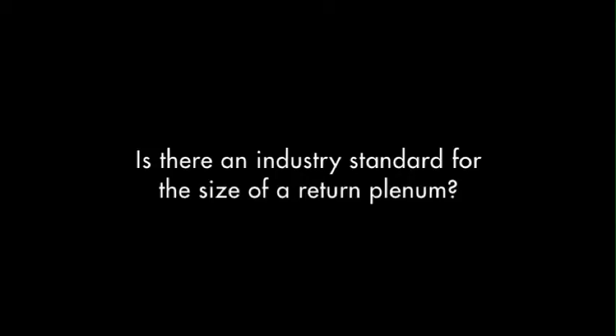I've not really run into any constraints about it being too big. I have run into constraints about it being too small. Fortunately, there's a relatively simple device called a Ductulator. Believe it or not, there is this Ductulator, and it was built in the 50s, 60s, that can give you a good rule of thumb on the size of the duct versus the CFM that you need to go through.